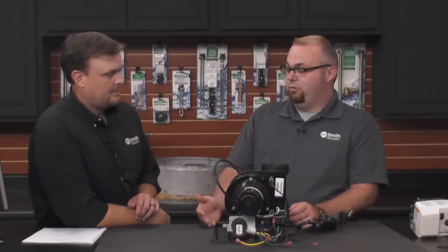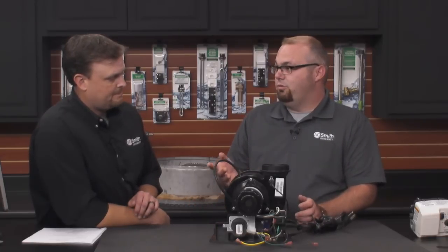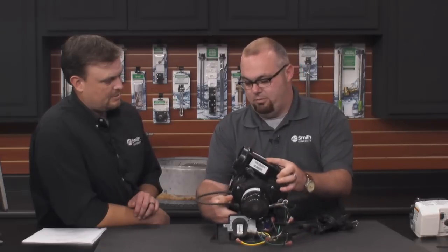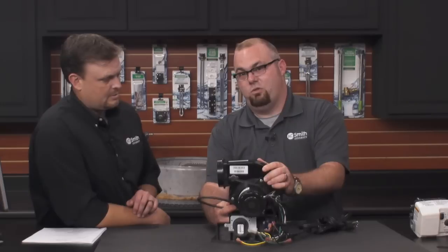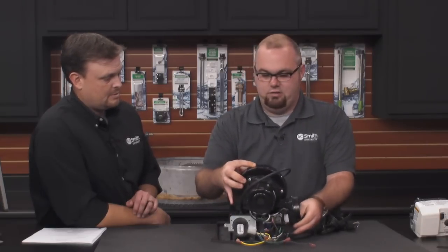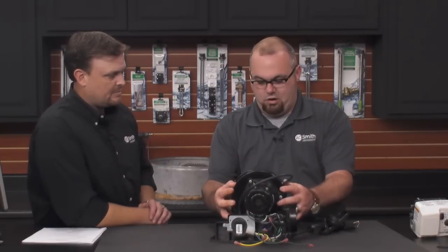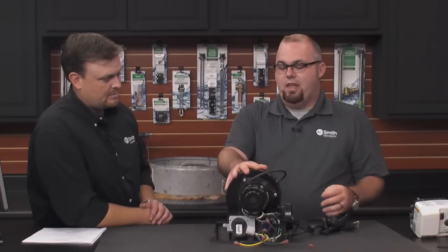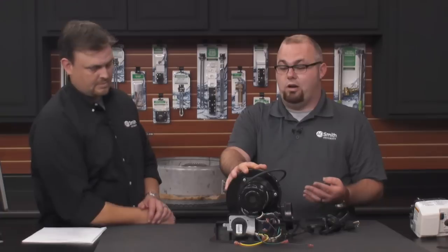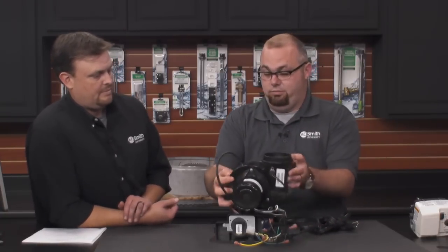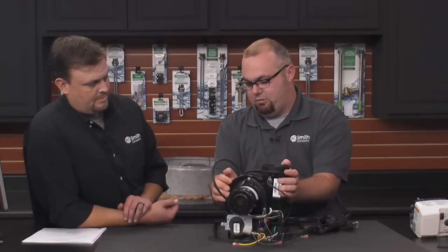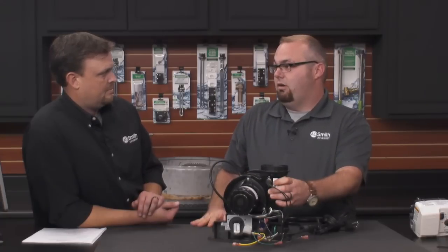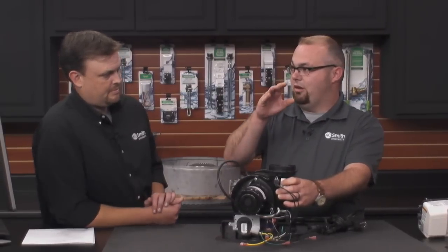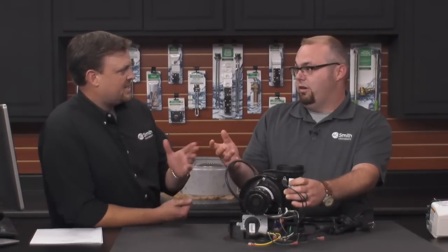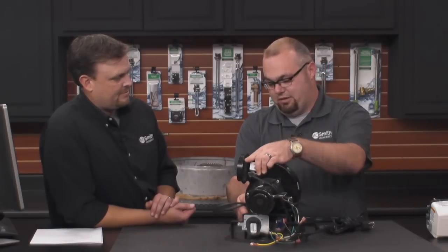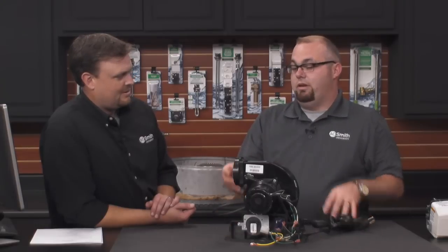Another great option about this, and we were talking about venting versatility earlier, is that the blower is actually rotatable. I can take this out and actually turn the blower. As you see, it can be in this orientation, or I can turn it and put it in this orientation. I have 4 bolts on the back that allow me to rotate it. This is an excellent option if you have an installation with low overhead clearance. On most power vents and most of the water heaters this is replacing, the venting comes right out of the top of the blower. On a lot of older power vents, you have to come up a certain amount of footage or so many inches before you elbow it. But on this heater, I can avoid that turn because I can turn the blower either way and it's already going in the right direction.